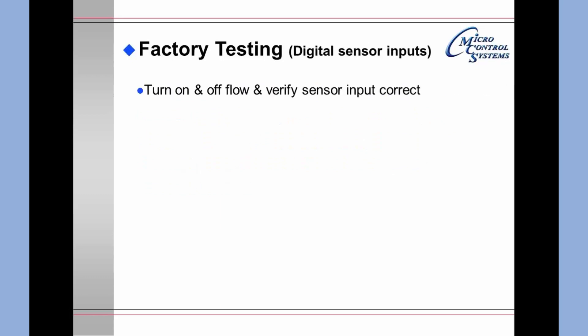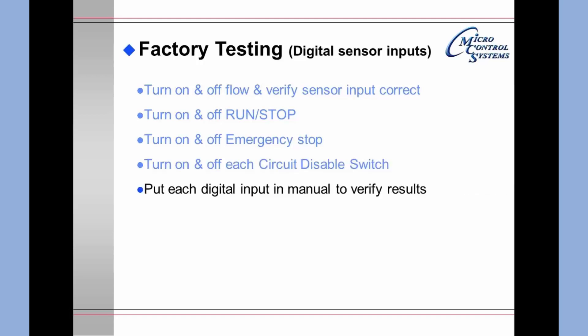For digital sensor inputs, you will turn on and off the flow and verify that the sensor input is correct. You will turn on and off the run stop switch and verify that it is correct. You will turn on and off the emergency stop switch and verify that it responds correctly. You will turn on and off each circuit disable switch and verify that the correct circuit shows up as disabled or shut down. Then put each digital input in manual to verify the results.